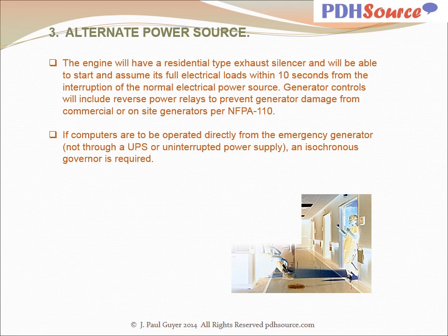The engine will have a residential type exhaust silencer and will be able to start and assume its full electrical loads within 10 seconds from the interruption of the normal electrical power source. Generator controls will include reverse power relays to prevent generator damage from commercial or on-site generators per NFPA 110. If computers are to be operated directly from the emergency generator, not through a UPS or uninterruptible power supply, an isochronous governor is required.